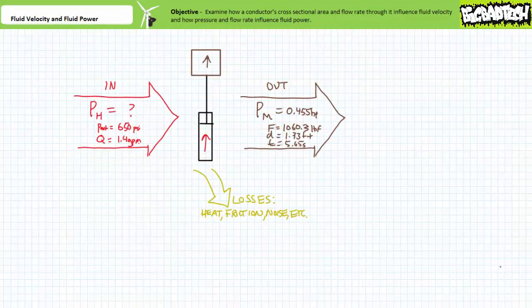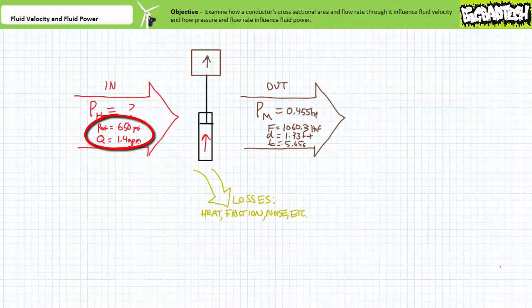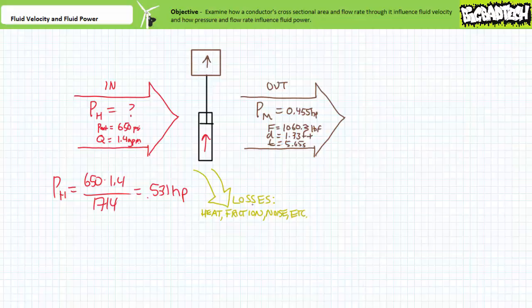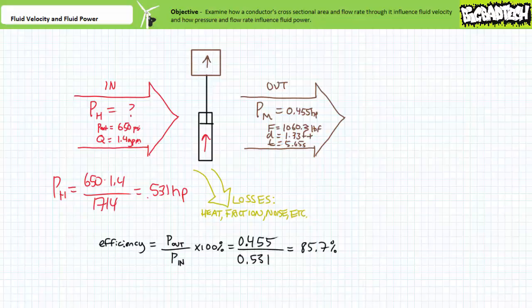This simple example assumes 100% efficiency — an obvious fallacy. Given an actuator is a fluid power to mechanical power converter, only a portion of fluid power input actually gets converted into usable mechanical power, the rest being lost to leaks, friction, heat, or noise. If the actuator supplies 0.455 horsepower of output but the observed input is 650 psi and 1.4 GPM — yielding approximately 0.53 horsepower input — then this actuator is approximately 85.7% efficient.